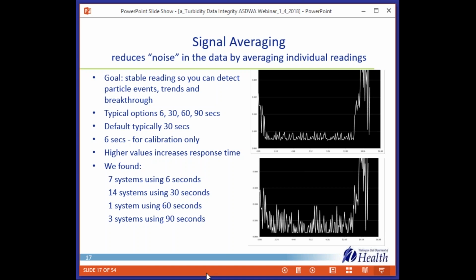On the 90-second, we thought that was pretty long. So we tried an experiment with the filter offline. We lifted the turbidity sensor up off the body to simulate a high reading. And then we had the operator watch the SCADA screen to see how long it took for the high turbidity to show up there. And 90 seconds is an amazingly long time when 2 people from the health department are standing over your shoulder watching a screen that doesn't move.